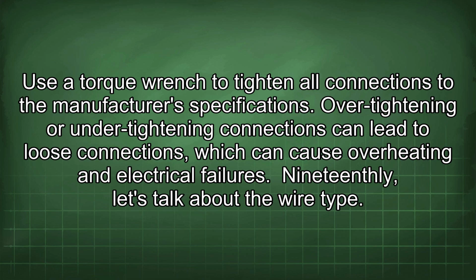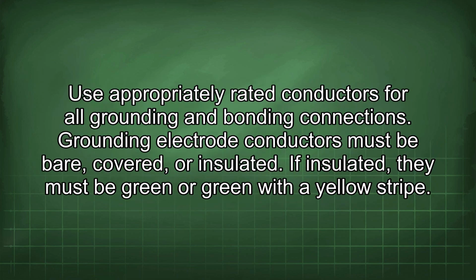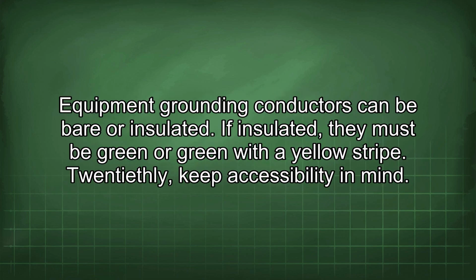19thly, let's talk about the wire type. Use appropriately rated conductors for all grounding and bonding connections. Grounding electrode conductors must be bare, covered, or insulated. If insulated, they must be green or green with a yellow stripe. Equipment grounding conductors can be bare or insulated. If insulated, they must be green or green with a yellow stripe.